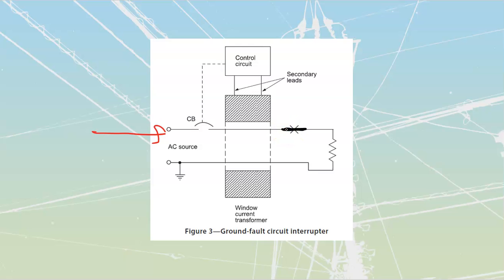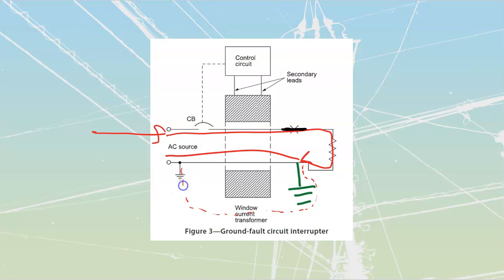If I were to go and have a fault on this side, it would just result in too much current that would travel through. A fault in the ground over here would result in ground current that's going to go back to my transformer and trip it out. We will look at that inside of grounding and bonding. For now, ignore it. Let's talk about an actual ground fault that's going to go and happen on the ground side. And this is where there's danger, because what happens inside of a ground fault is that all of my current that was traveling through gets up to this point, and anytime that there's a junction, my current is going to split. The bulk of my current is still going to travel back through here, but a little tiny bit of it, because there is an alternate path, is going to go and sneak its way back out and around.